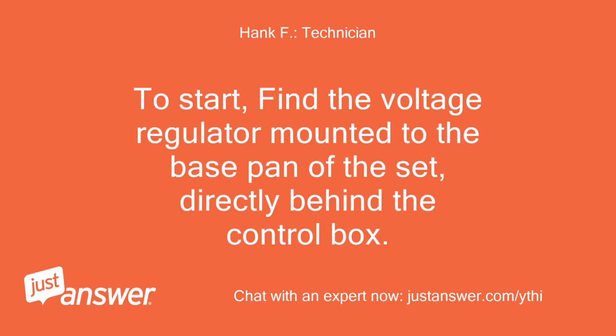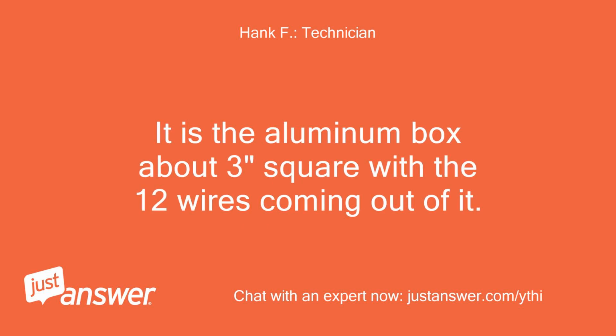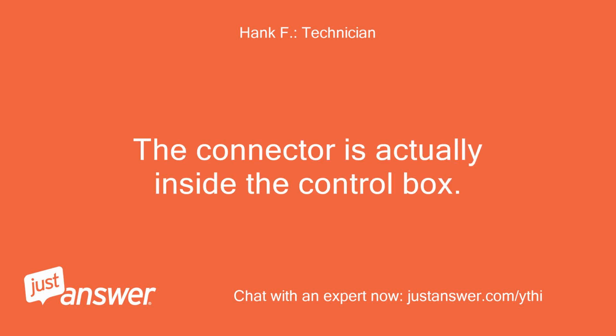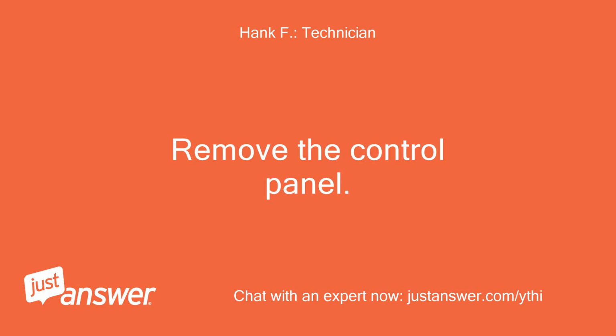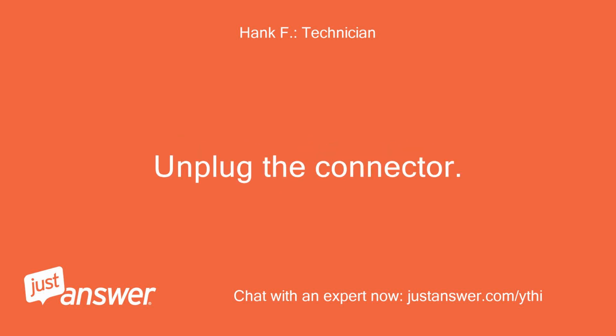To start, find the voltage regulator mounted to the base pan of the set, directly behind the control box. It is the aluminum box about 3 inches square with the 12 wires coming out of it. The connector is actually inside the control box. Remove the control panel. Unplug the connector.